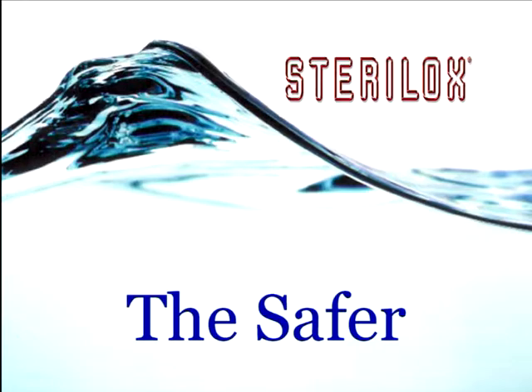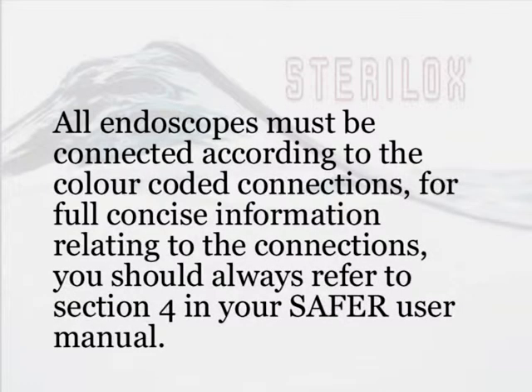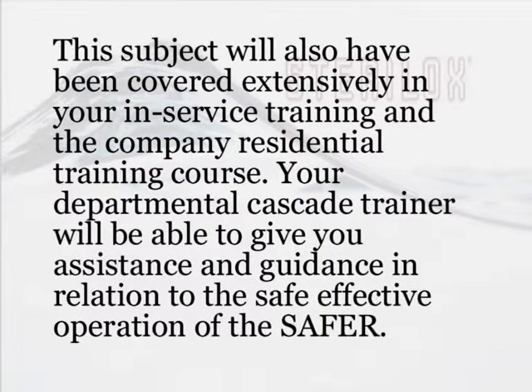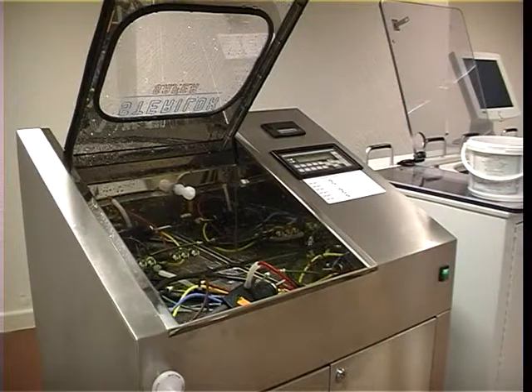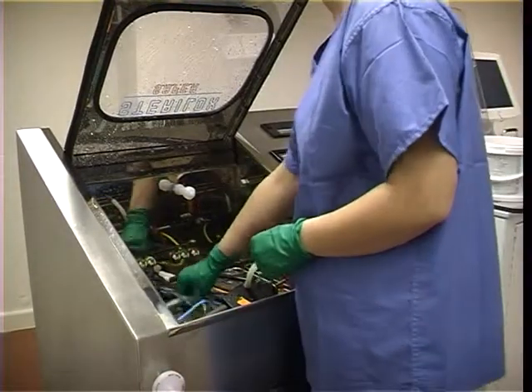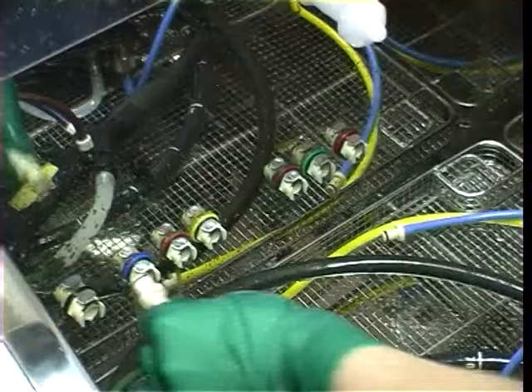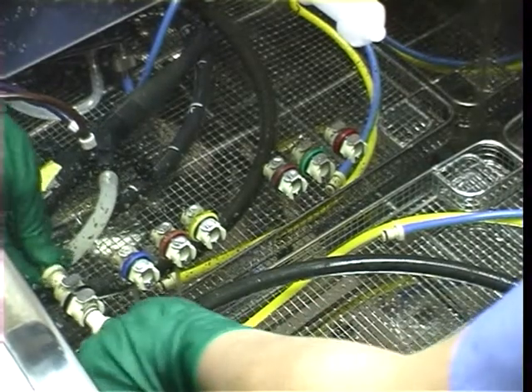The Safer. All endoscopes must be connected according to the color-coded connections. For full, concise information relating to the connections, you should always refer to Section 4 in your Safer User Manual. This subject will also have been covered extensively in your in-service training and the company residential training course. Your departmental cascade trainer will be able to give you assistance and guidance in relation to the safe, effective operation of the Safer. Any port that is not needed for flowing your endoscope must have a blank bulkhead and tube inserted before the cycle, or the cycle will alarm and abort.